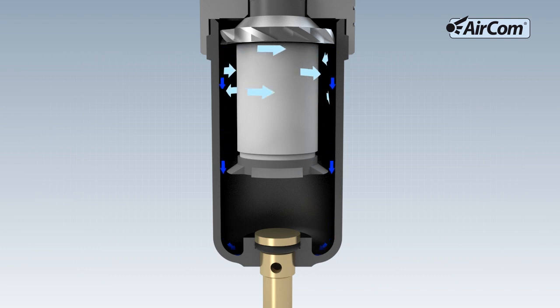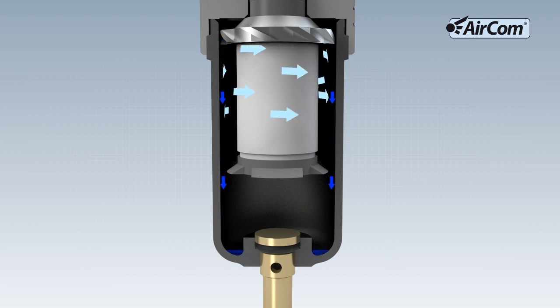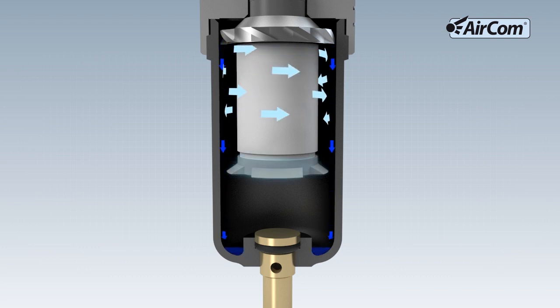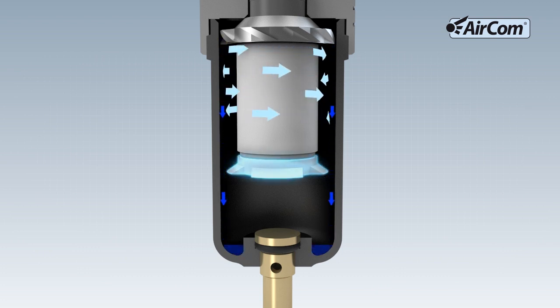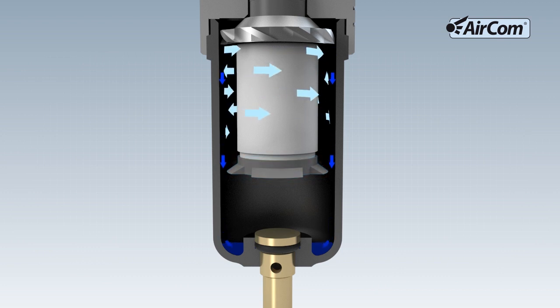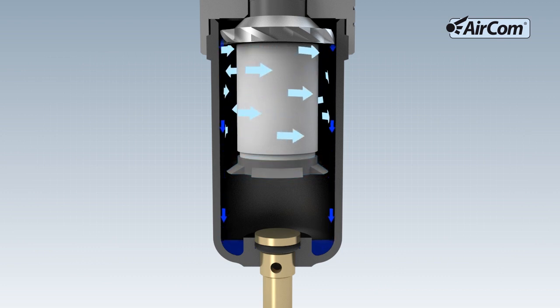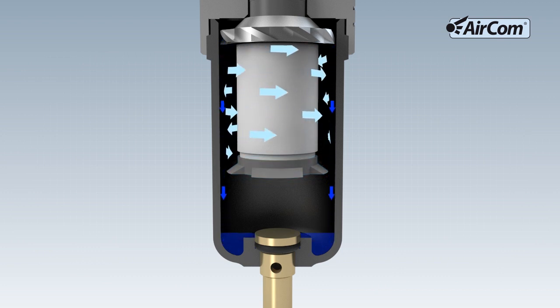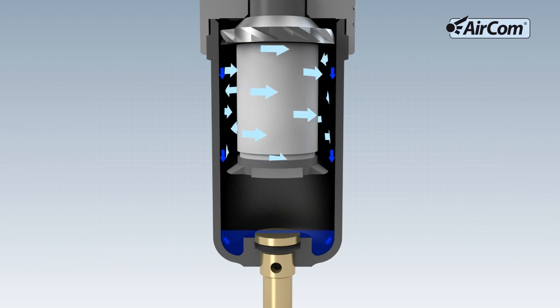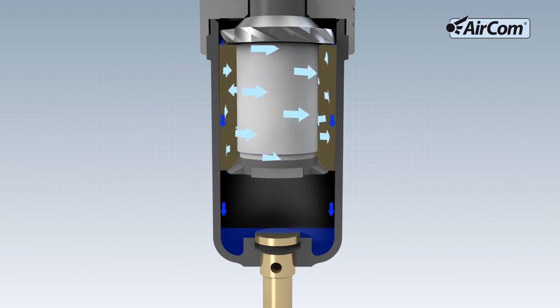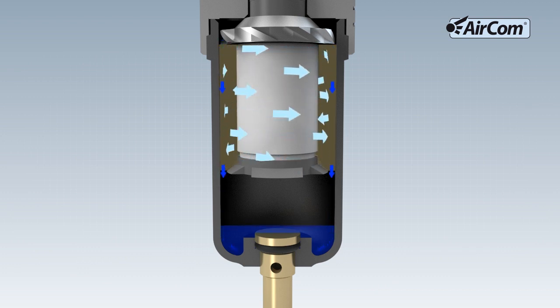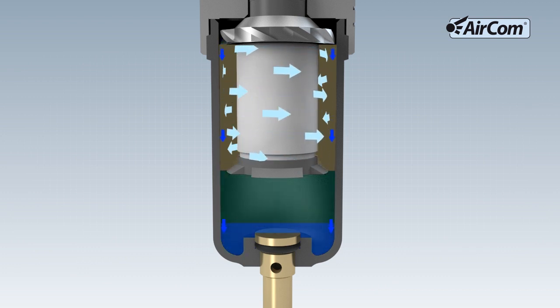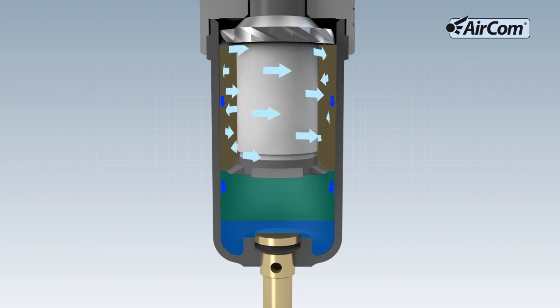flings water particles in the air against the filter wall, which then flow down to the container's base. The divider prevents the collected water, referred to as condensate, from being picked up by the airflow again. It divides the filter into a flow zone and a slowdown zone.